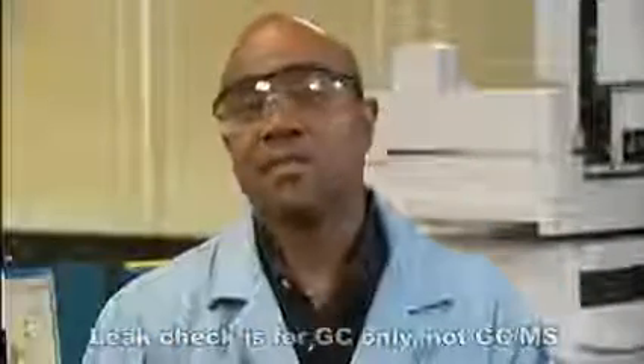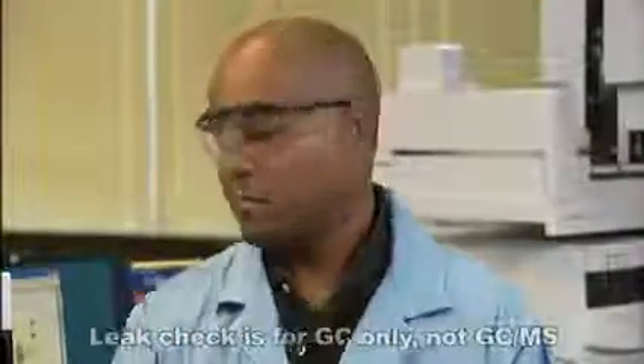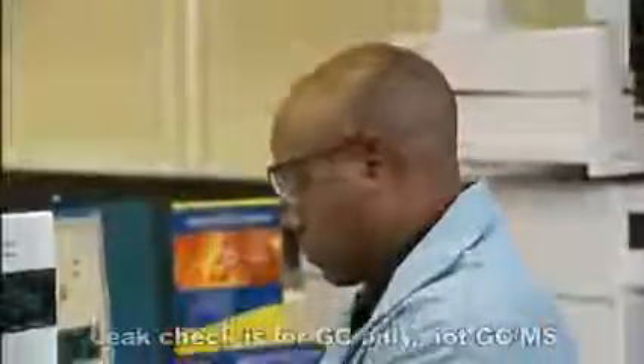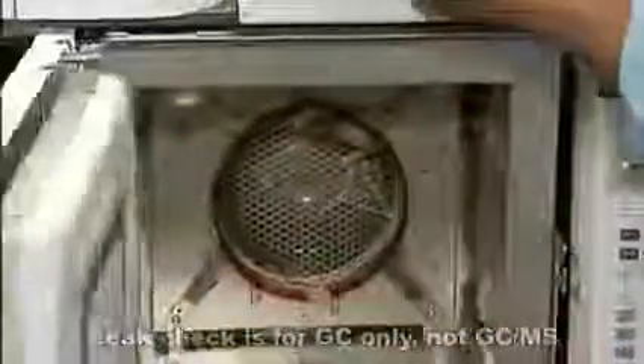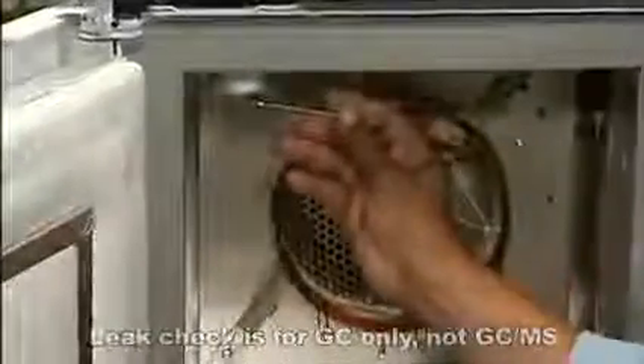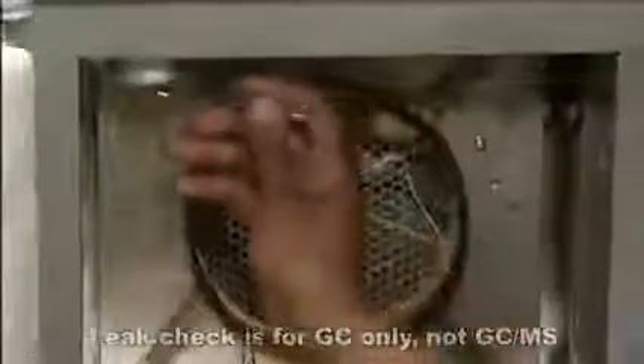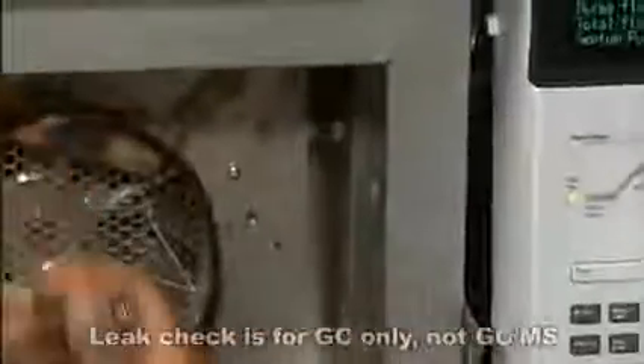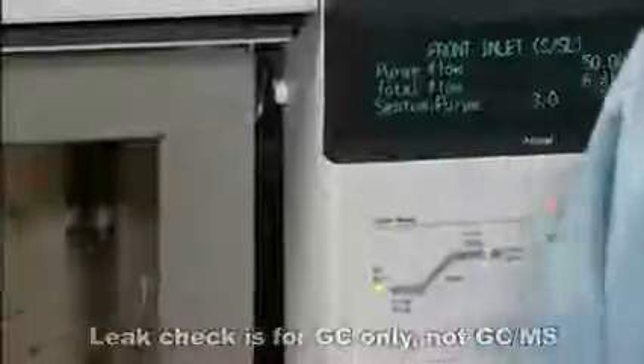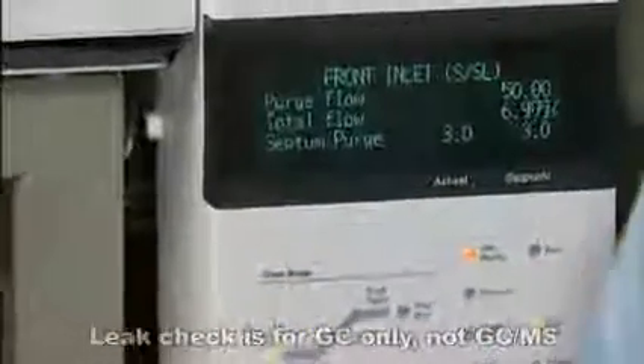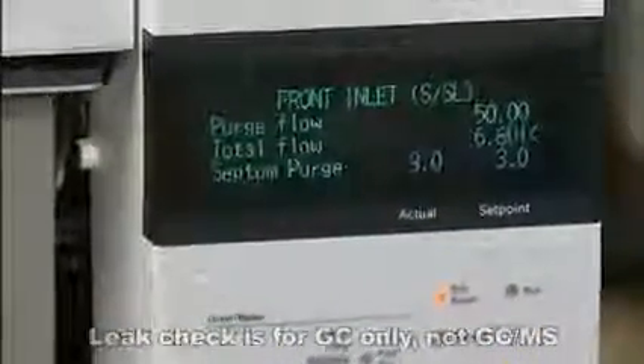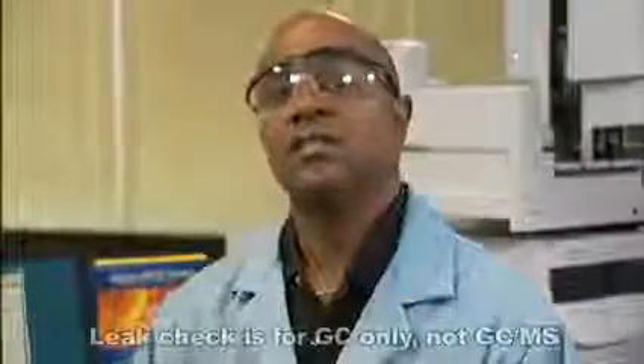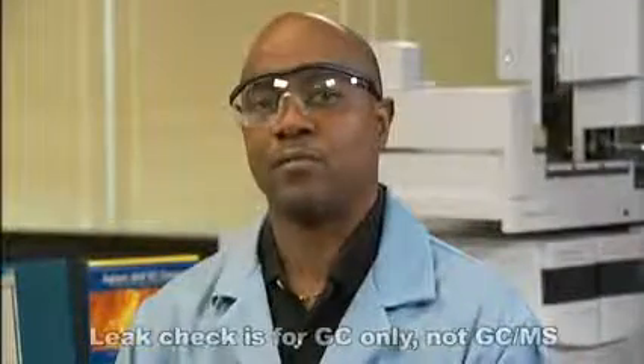That's not it. Now I'll try the column nut. Okay, there we are. You see how the total flow has dropped to less than 10 mils a minute? This is probably good enough for our example.